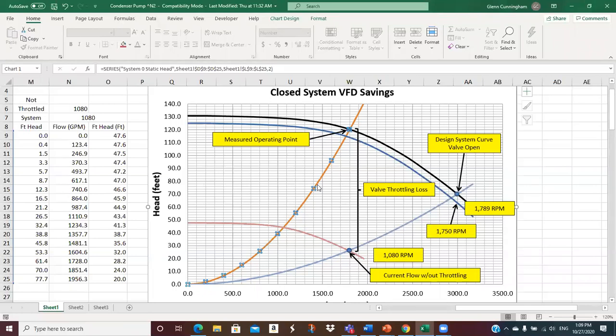What had happened is they took out a chiller. Instead of having two chillers, they had one chiller, and they were too cheap to do anything to the pumps, or just didn't. And the chiller people come in and say, you're pushing way too much water through that condenser, you're going to wreck the condenser. So then the chiller people start throttling the valves to protect the condenser, but the pumping energy just becomes a huge waste.